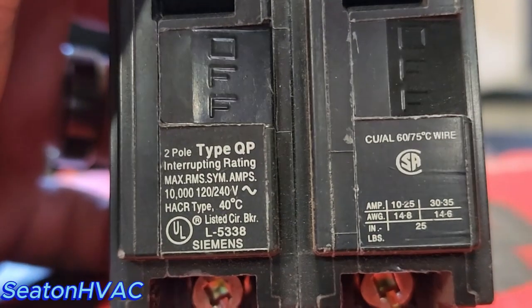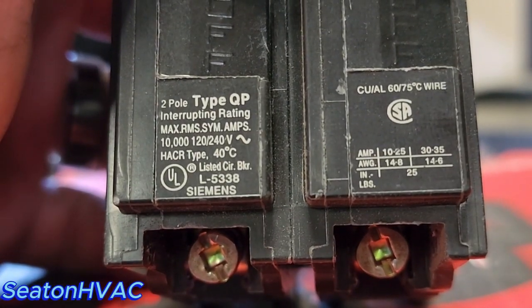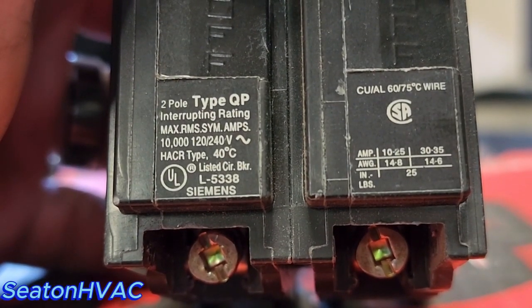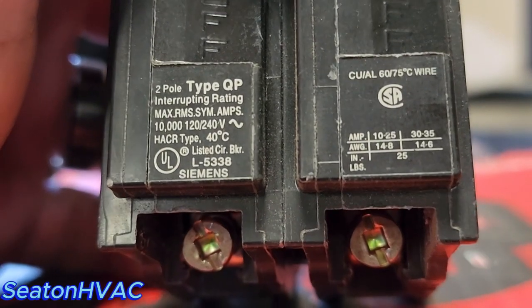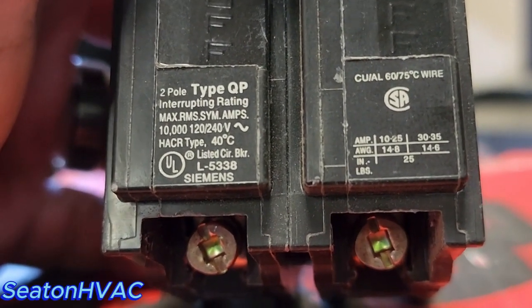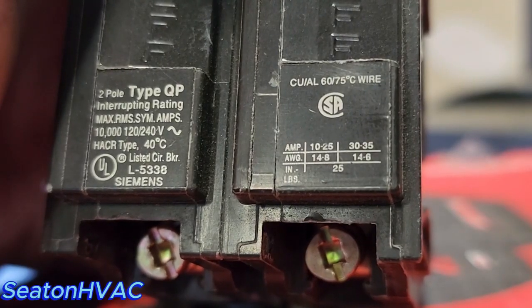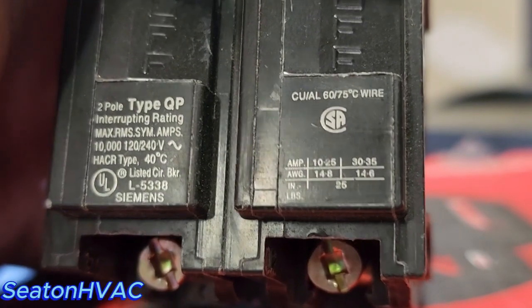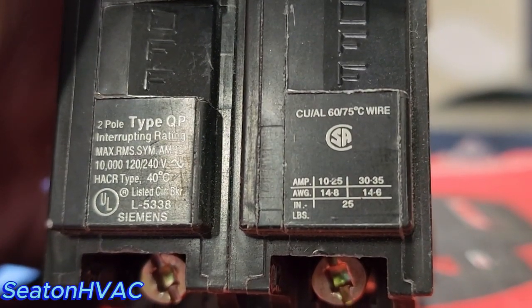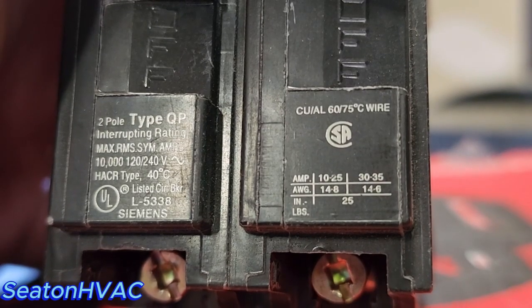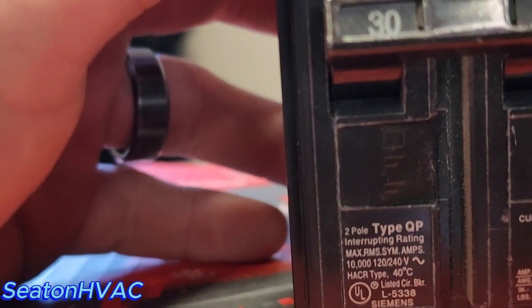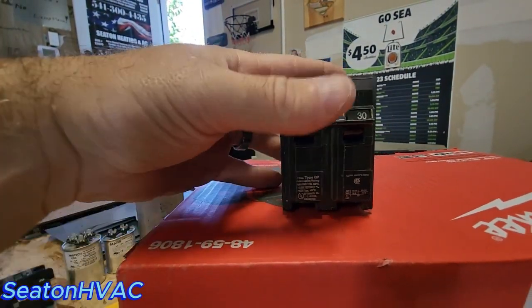2-pole type QP, that's just the brand, Siemens. It gives you an interrupting rating, maximum RMS amps. You'll never really need to know what all those little numbers mean if you're just working on it. But somebody installing these definitely wants to pay attention to the numbers on these breakers. So there's the first breaker. I won't get into fine detail with these other ones. I just want to show you what the other types are. So let's move on. All right, here's another breaker.